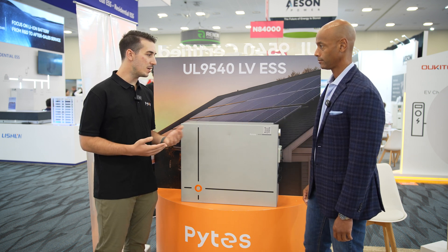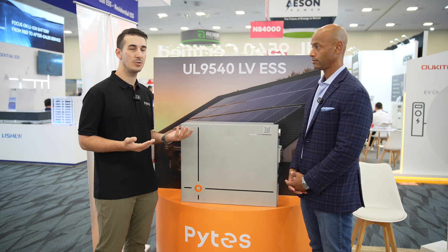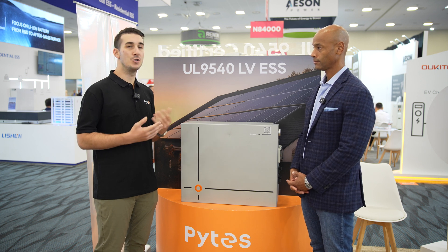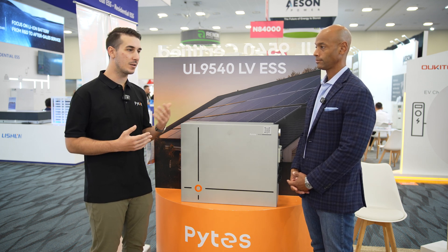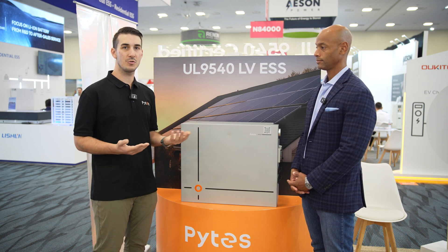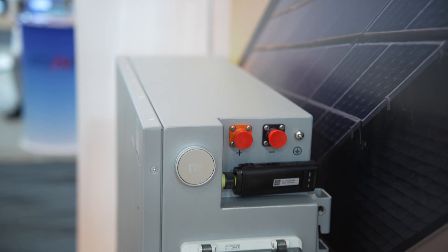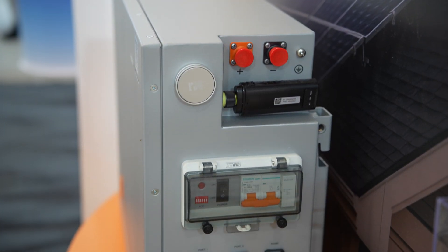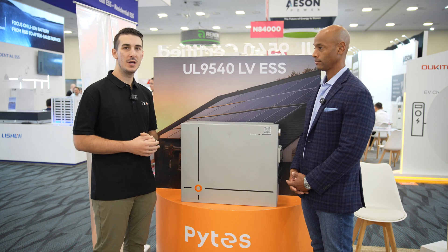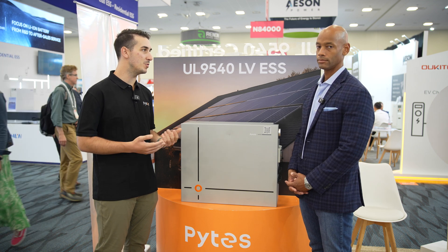Generally speaking, Pytes batteries have an extremely low rate of failure — 0.3% or lower, so about three out of every thousand batteries. The majority of those issues come down to things like a failed BMS or power board, which makes our batteries extremely field serviceable. It's very rare that you'd have to dismount, disassemble, and ship a battery back to us for replacement.